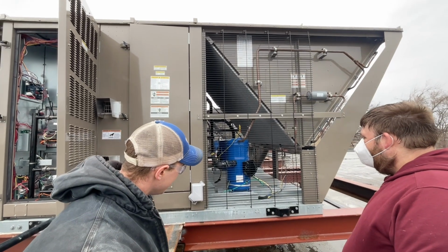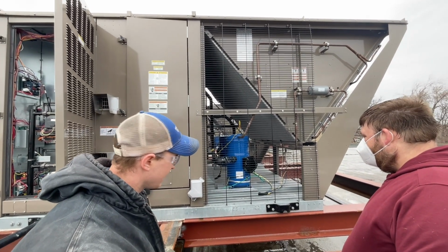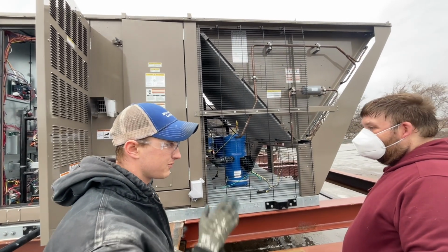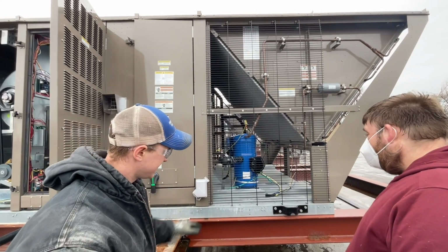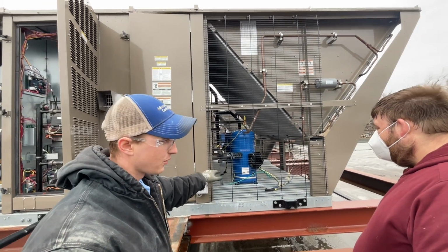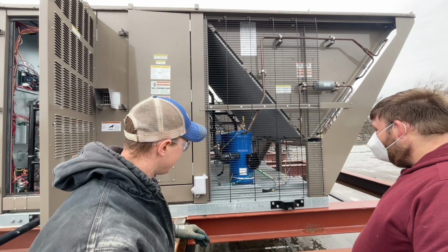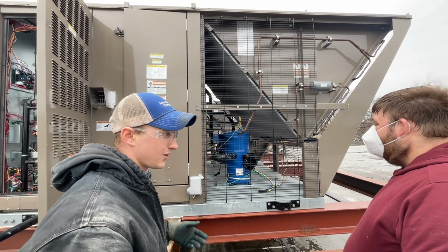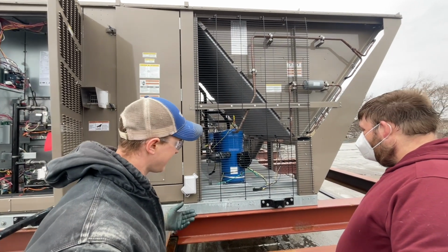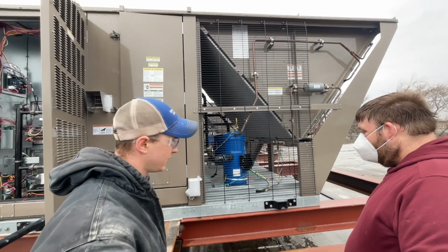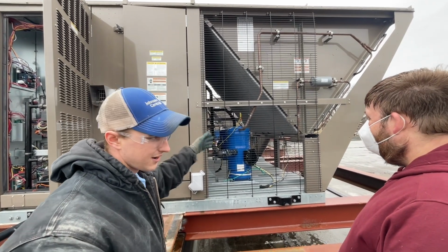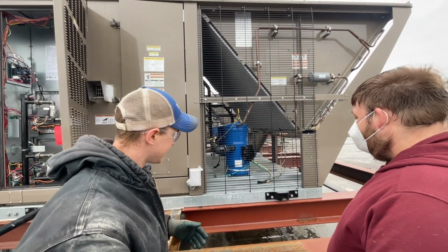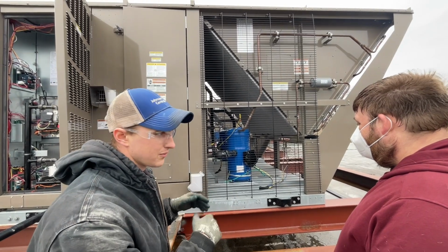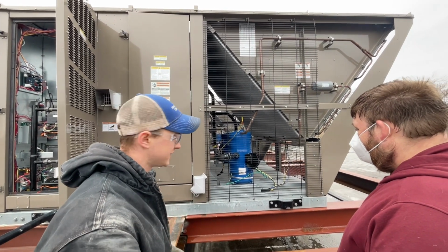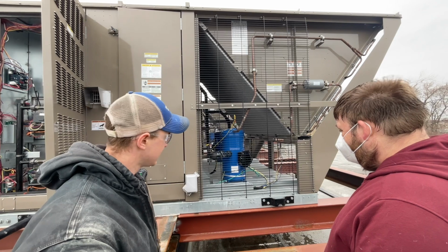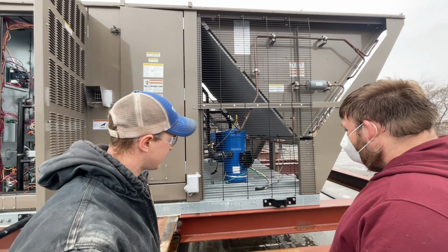I don't know what you're doing maintenance wise, but if you are going to be starting up cooling each year, a good thing to check is make sure that the heaters are in operation, because what the heaters do is keep the refrigerant out of the oil, and it warms the oil up. The main thing is to keep the refrigerant out of the oil, so when they start up for the season or at cold temperatures like this, it doesn't have a bunch of liquid refrigerant mixed in with the oil, because that's just going to wash out the bearings, and the compressor takes a lot of damage.